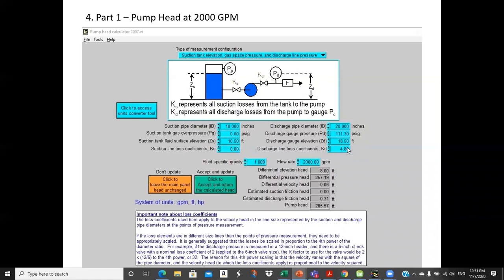And so that gets inserted here as the discharge line loss coefficient, the sum of them for those two valves right here. It doesn't make a whole lot of difference in this case. It changes it a very small amount. But at any rate, having done that, with the rest of the information put in, we get a pump head of 265.57. And so let me see.